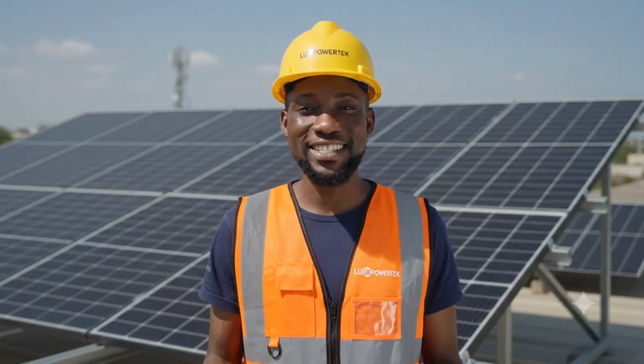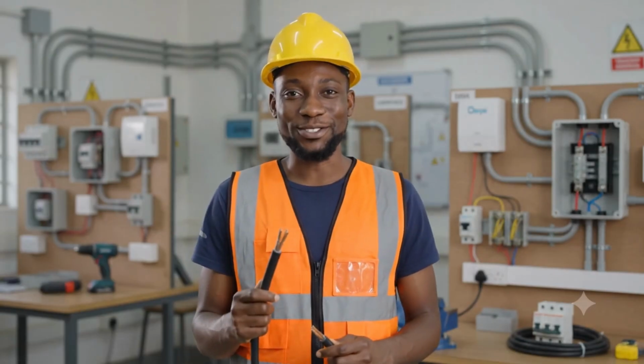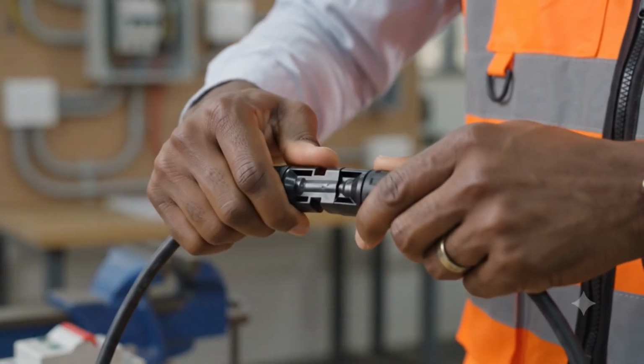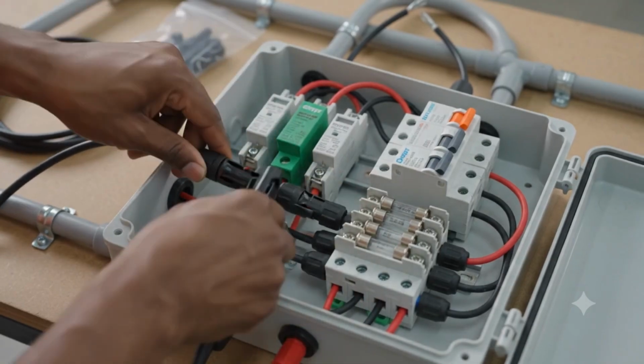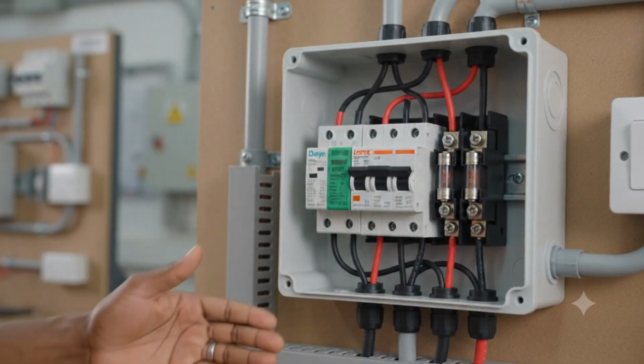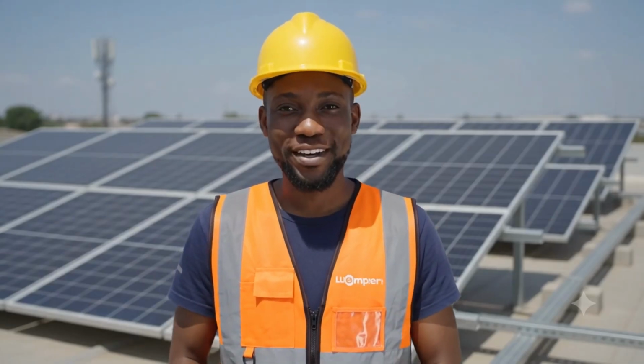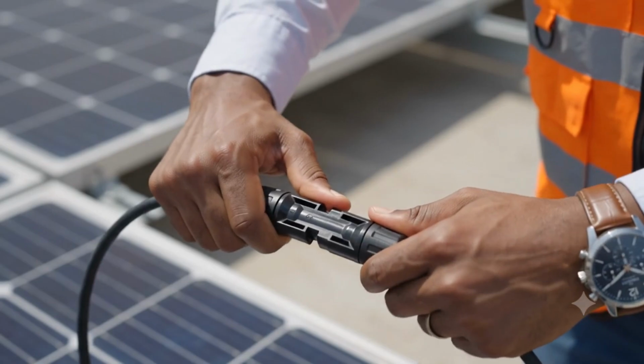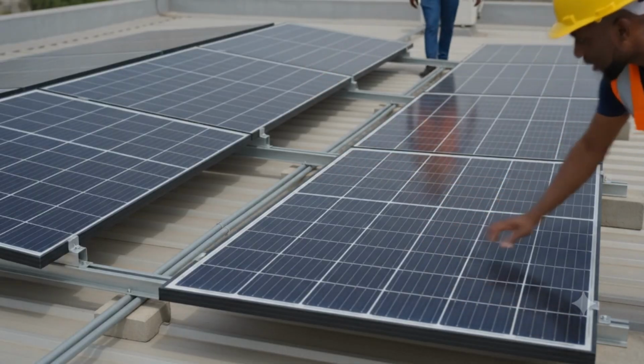To increase efficiency, now we connect our solar panels using MC4 connectors and thick cables, routing them through a combiner box equipped with fuses and breakers to match the inverter voltage. We connect the solar panels on the roof in 12 series and 2 parallel strings, giving optimal voltage and current.